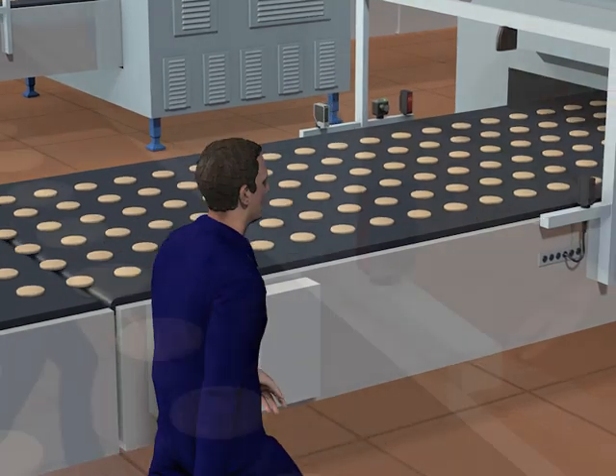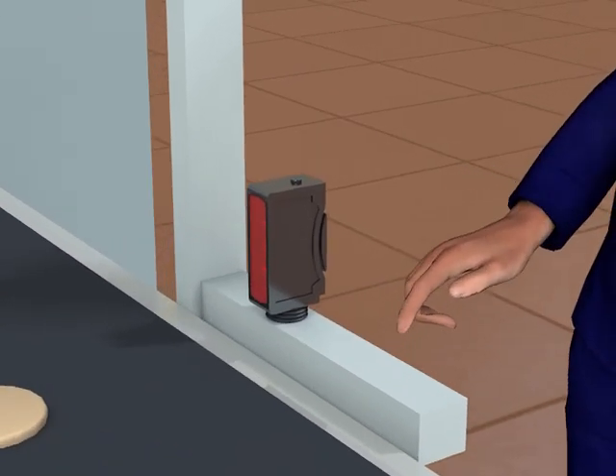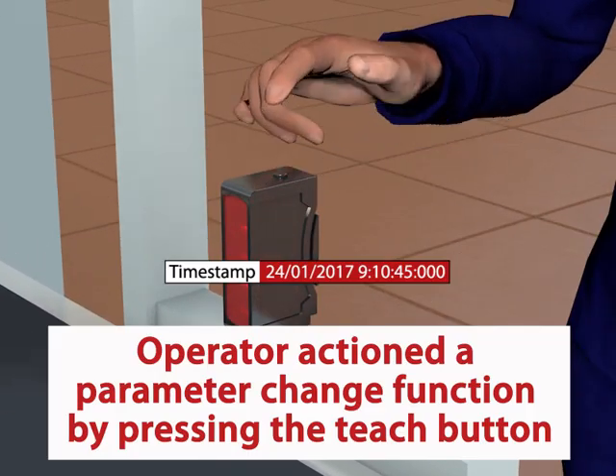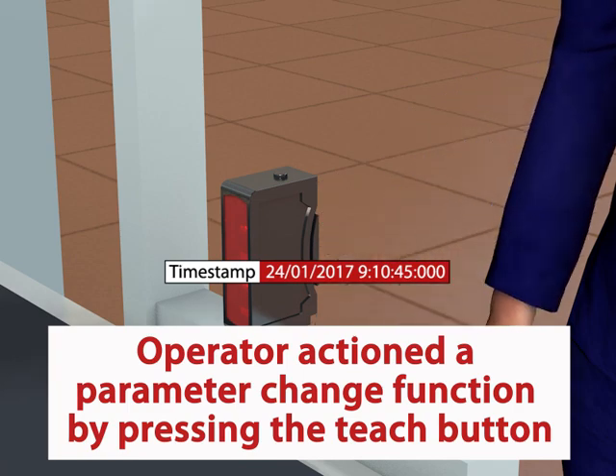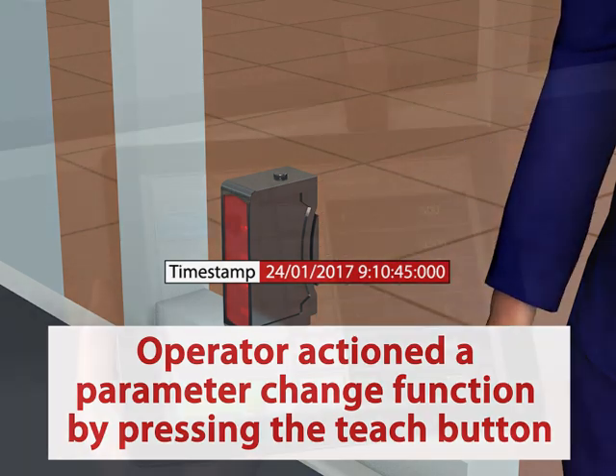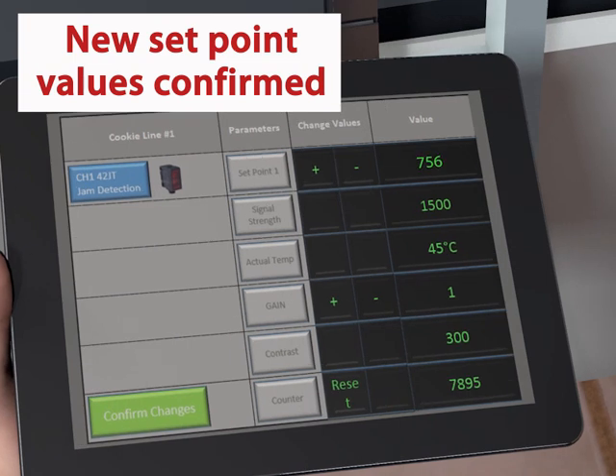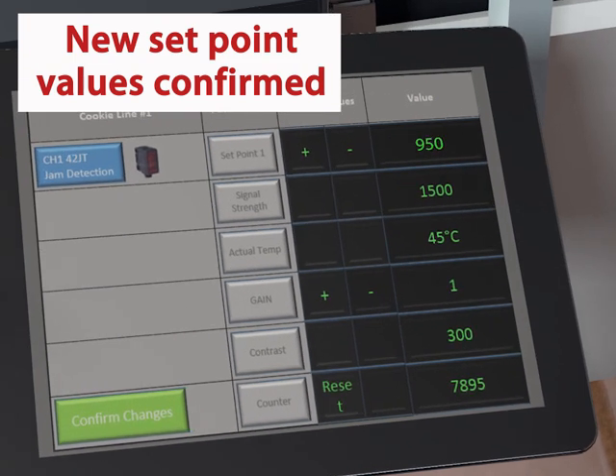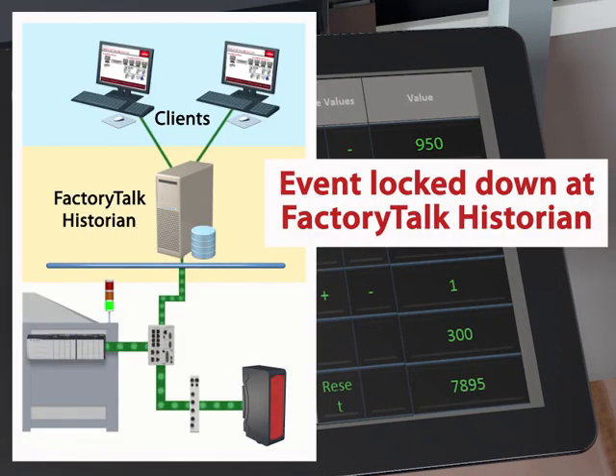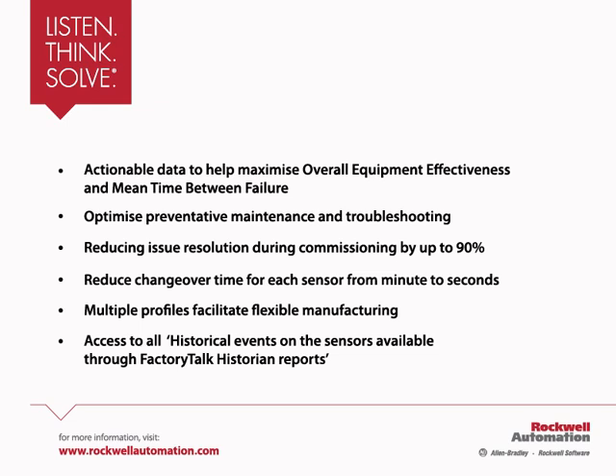On another part of the equipment, the operator actions a parameter change by pressing a teach button on a smart sensor. The new set point parameters are stored on the device, and the parameter change event is time-stamped and communicated over Ethernet IP to the controller and then passed again to FactoryTalk Historian. FactoryTalk Historian maintains a report on all parameter changes and the times of those changes in order to monitor device operation and improve equipment effectiveness.